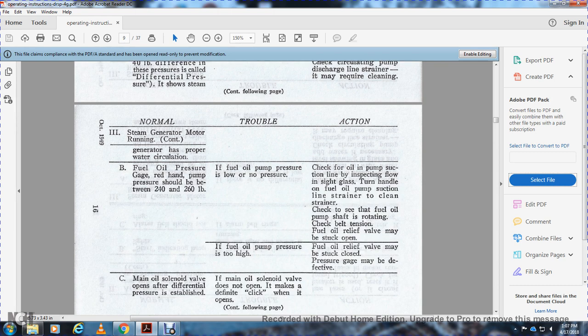Alright, B, the fuel oil pressure gauge red hand pump pressure should be between 240 and 260 pounds normal. Trouble: if the fuel oil pump pressure is low or there is no pressure, check the oil pump suction line by inspecting the flow in the sight glass. Turn the handle on the fuel oil pump suction line strainer to clean the strainer. Check to see if the fuel oil pump shaft is rotating. Check the belt tension, and check whether the fuel oil relief valve is stuck open.